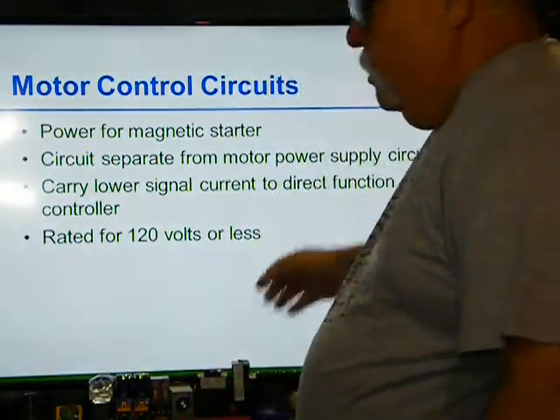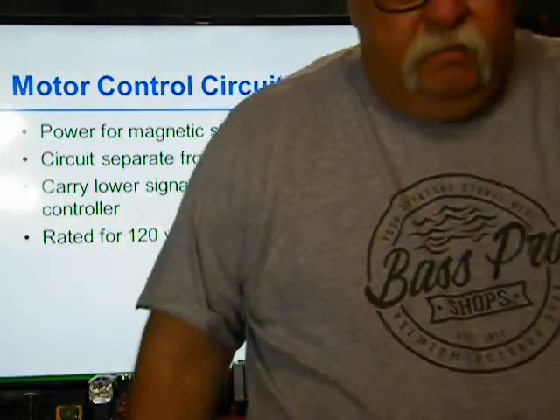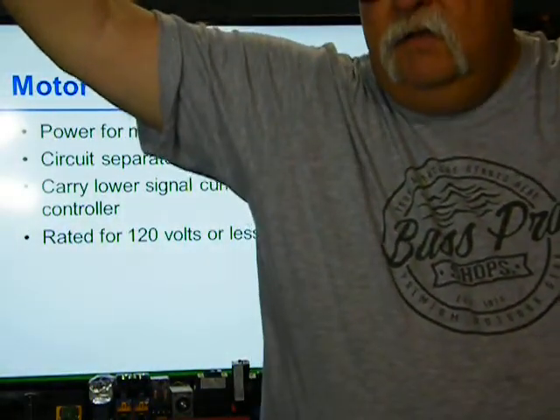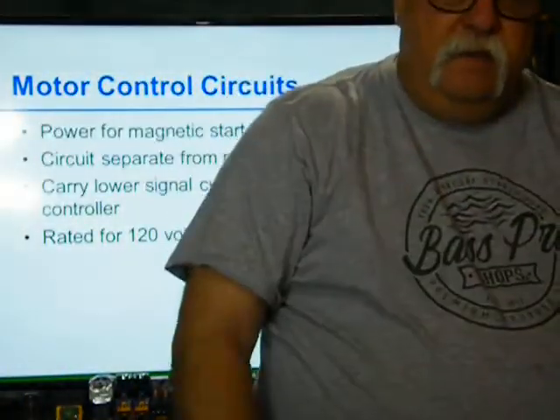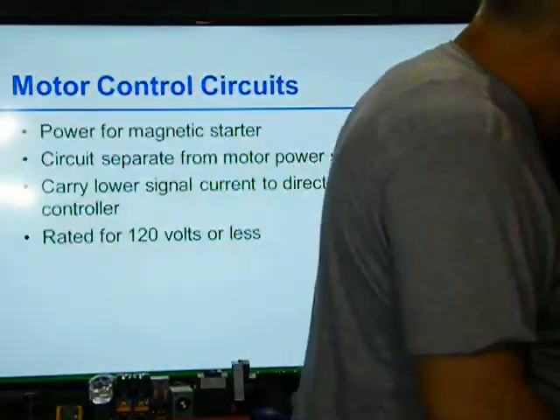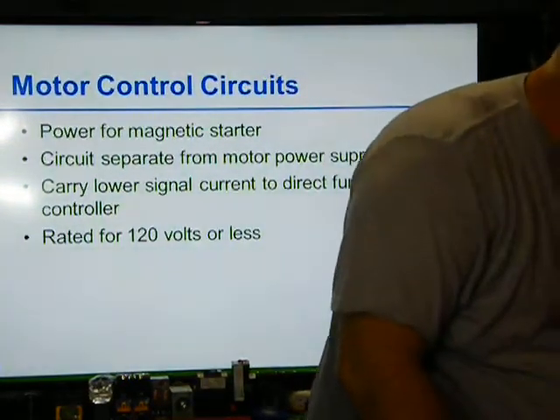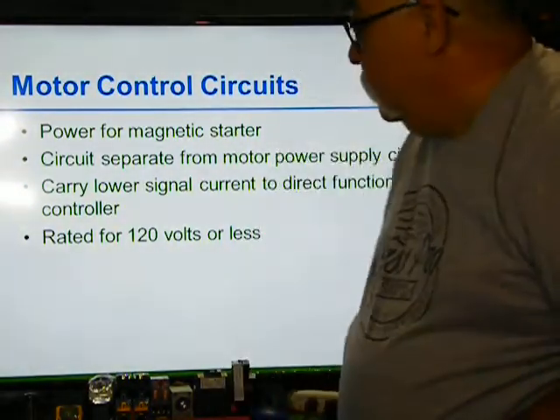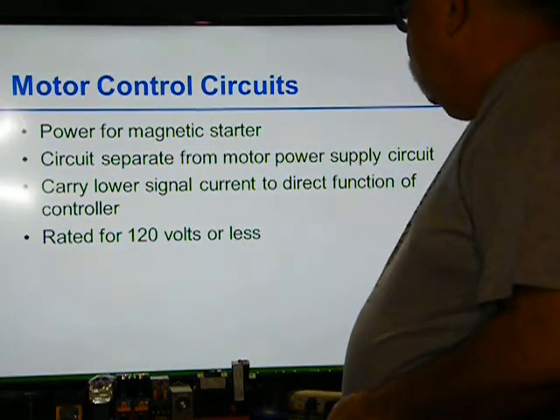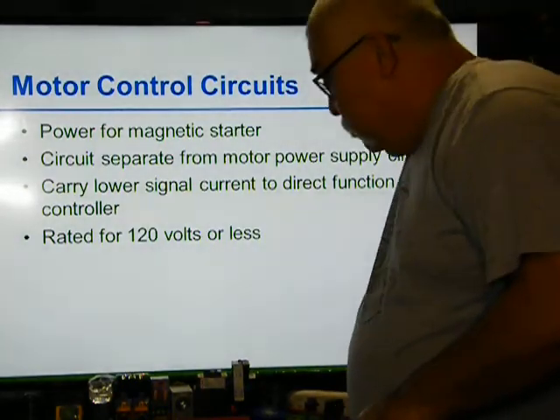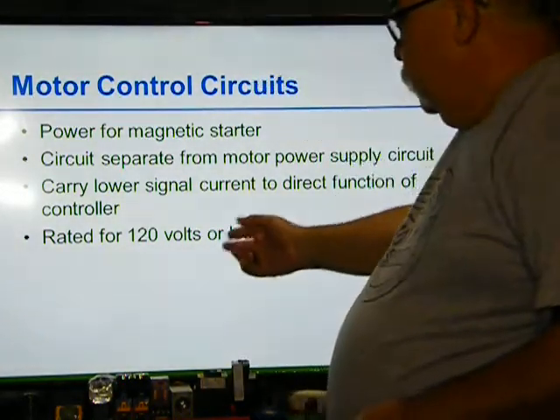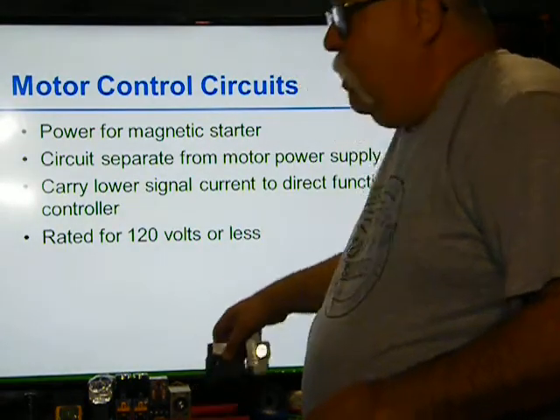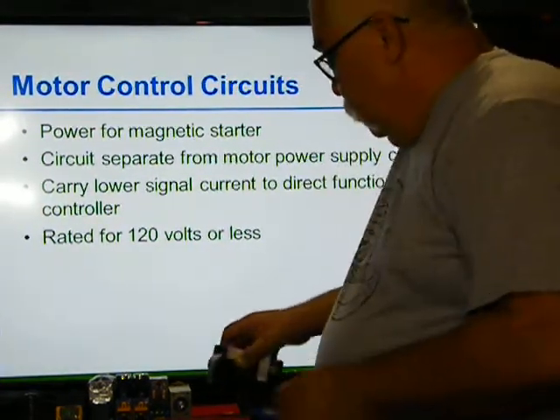The other way of getting power is bringing a separate circuit in. Like I have a motor control center that has 40, 50 motors controlled out of that motor control center. So I bring a circuit in and I tie it in. I come off the panel. The panel might be on the motor control, or it might be elsewhere within that motor control center. It carries lower signal current to direct the function of the controller. When we get power, they're usually rated 120 volts or less. When we get power off the motor control, we go off and we control the circuit.